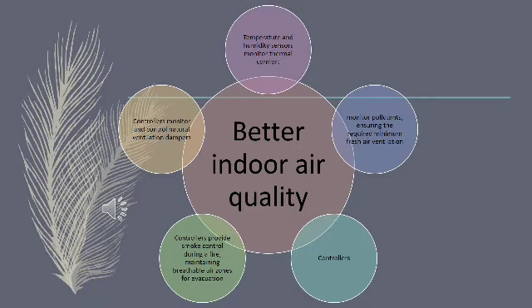VAV sensor allow each room or zone to be adjusted individually for each specific situation. Temperature and humidity sensor monitor thermal comfort. Carbon dioxide and carbon monoxide sensor monitor pollutant, ensuring the required minimum fresh air ventilation. Controller based on sensor input provide optimal zone ventilating, heating and air conditioning.